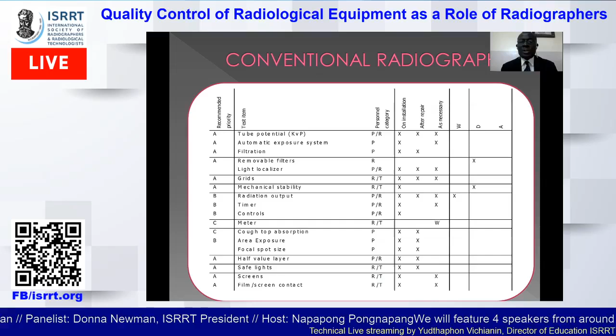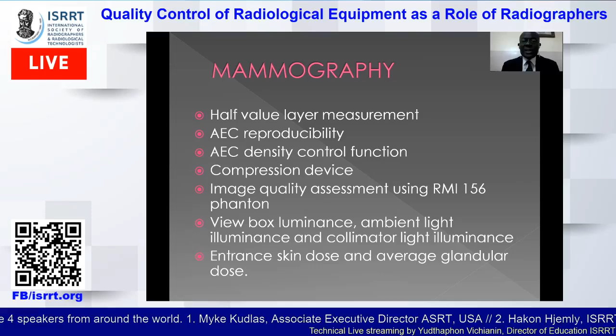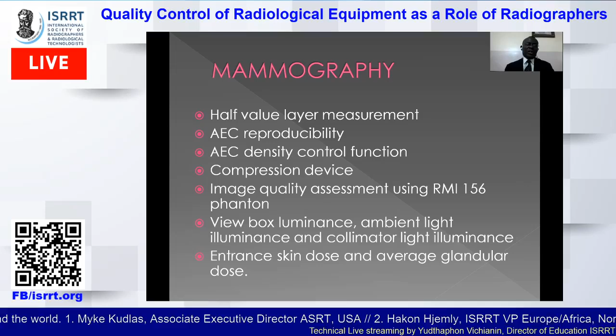In mammography, the criteria are half value layer measurement, automatic exposure control reproducibility, automatic exposure control density control function, compression device, image quality assessment, view box luminance, ambient light luminance, and collimator light luminance. It is also important to check the entrance skin dose and average glandular dose.